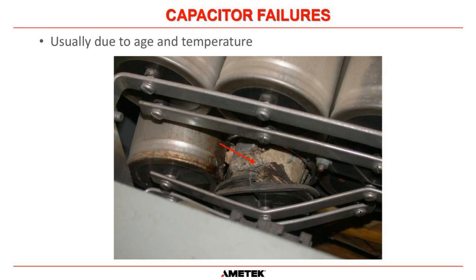And then eventually what will happen is, when the electrolyte dries out, there will start to be short circuits inside the capacitor, and those short circuits cause heat, and heat builds up pressure. And it's like a snowball effect. And eventually what will happen is when a DC capacitor fails, it fails with so much pressure that it can do what you see in this picture. It will completely rupture in an explosive form. And I can pretty much assure you that there would have been a huge amount of smoke from inside the capacitor when this capacitor failed.